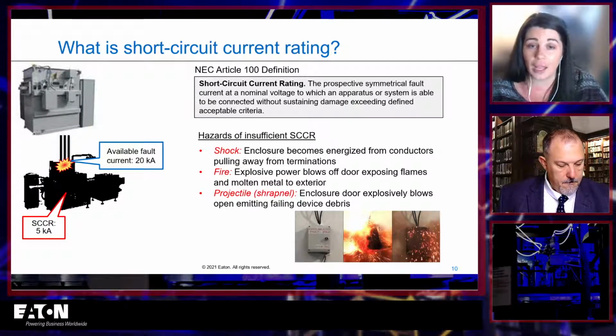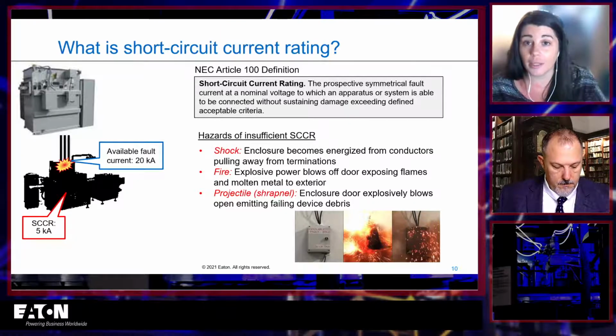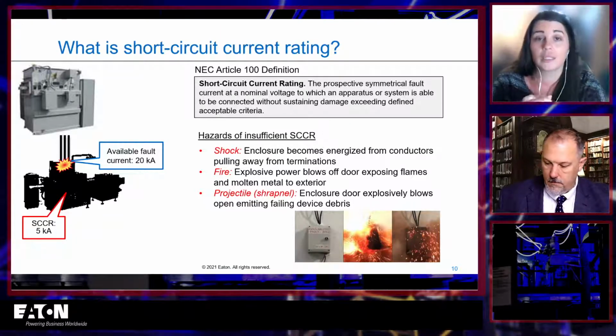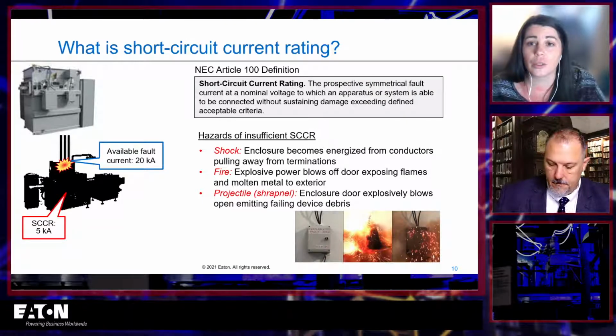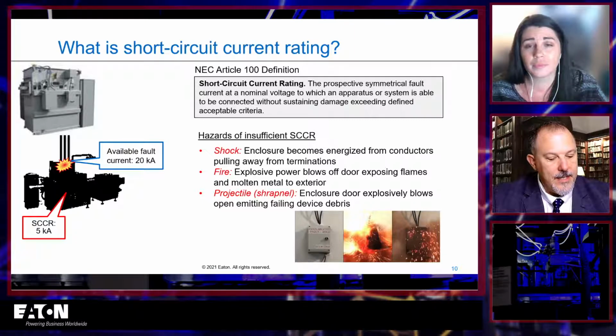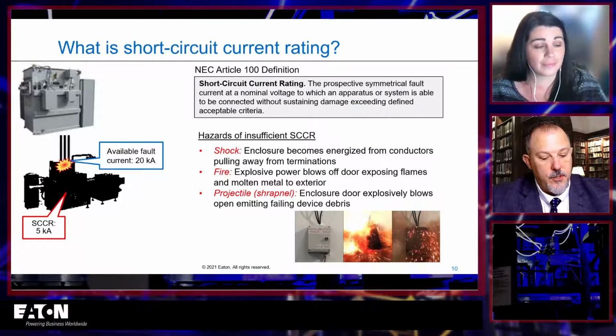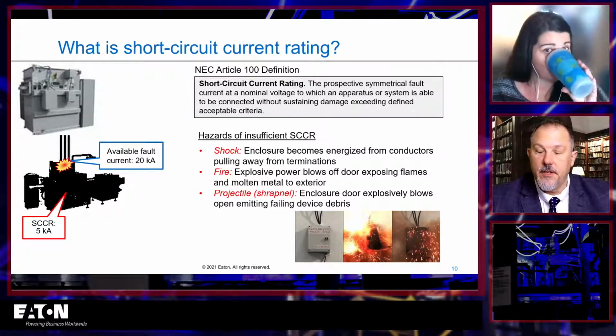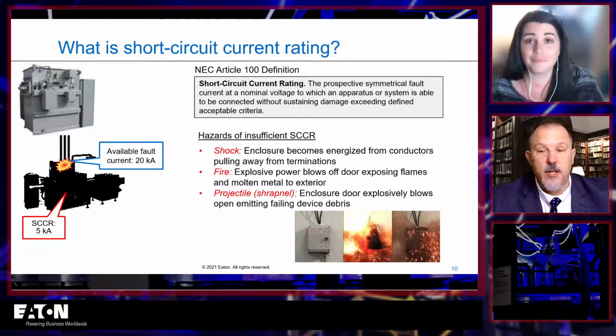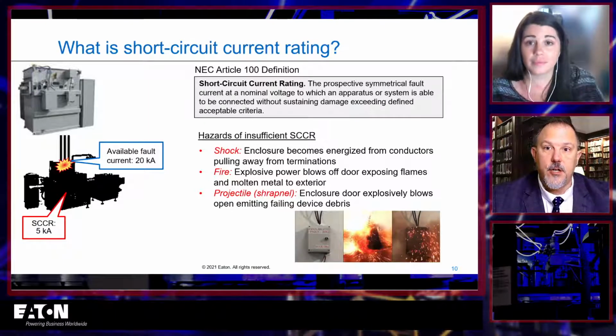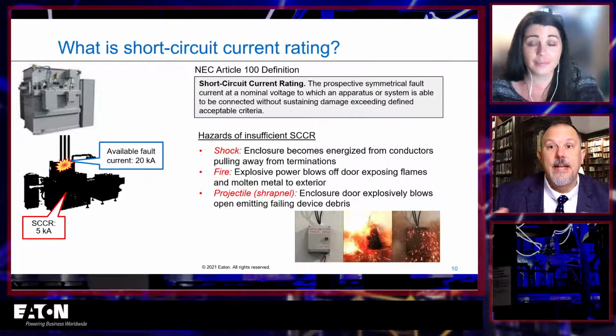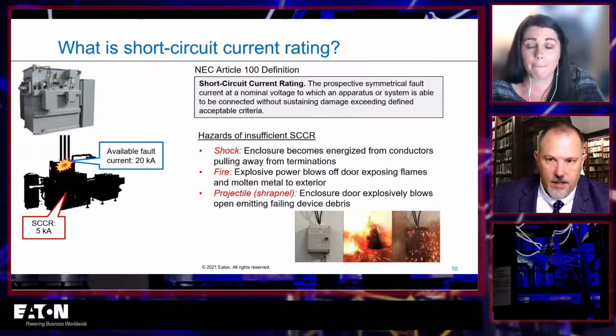But the big thing, again, is this is going to apply generally to your entire assembly. So whatever is inside your probably gray box, that whole assembly will have a short circuit current rating. And when you were talking about damage, in 110.10 it says to permit the circuit protective devices used to clear a fault to do so without extensive damage to the electrical equipment of the circuit. So it doesn't mean it's not going to have any damage. It could have damage. It may not be able to be placed back into service. It's just not going to create a shock hazard. It's not going to create that additional hazard of arc flash and all this other good stuff.